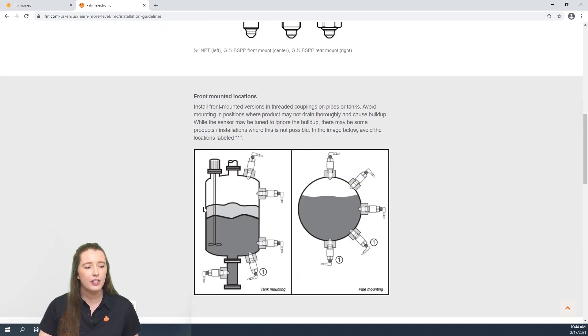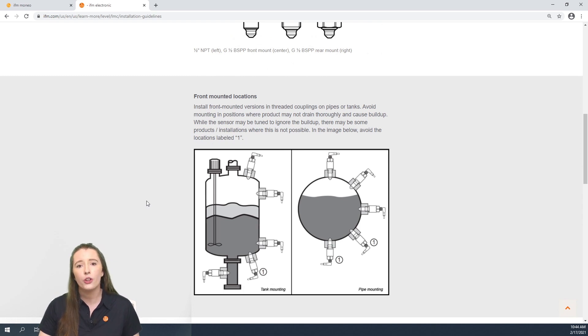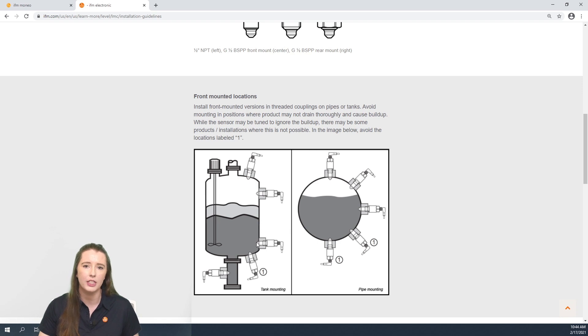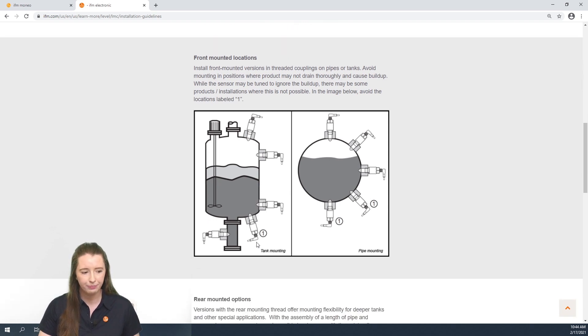Next we have a diagram that shows how the different front mounted versions can be installed in a tank or a pipe. Although these sensors have residue suppression technology, we still recommend avoiding installing it in the positions labeled 1 in each of these images to avoid any residue that just cannot be ignored.